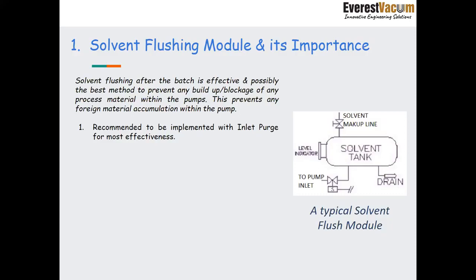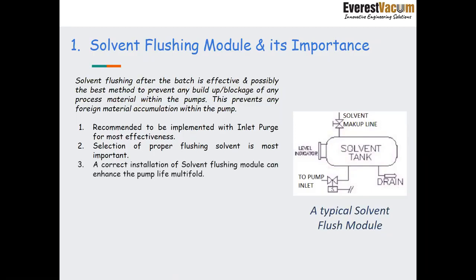The reason I already mentioned: an inlet purge is basically a nitrogen purge to break away the vacuum, because if the vacuum is too high, the purpose of liquid cleaning won't be achieved. So this is done to break away the vacuum levels and to ensure the effectiveness of this solvent flushing agent. Another critical parameter is the selection of the proper flushing solvent. It should have the capability to dissolve the contaminants. It should be miscible. And a correct installation of the solvent flushing module can enhance the pump's life multi-fold.